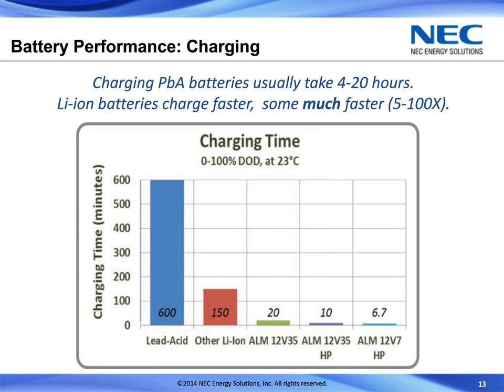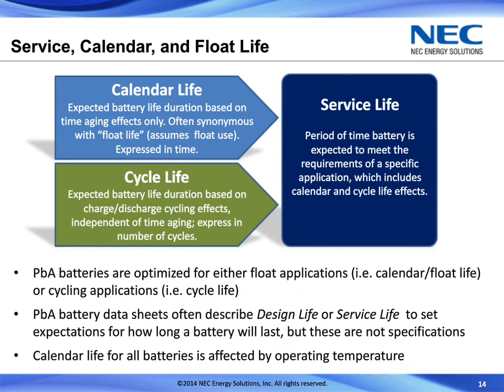Now, those are just 2 of the performance criteria. The other criteria looking at different batteries is how long will that battery last in a real-world situation. And there really are 2 major factors associated with that. The first is what we call the calendar life, which is often used synonymously, even though it's not necessarily exactly the same thing, as the float life.